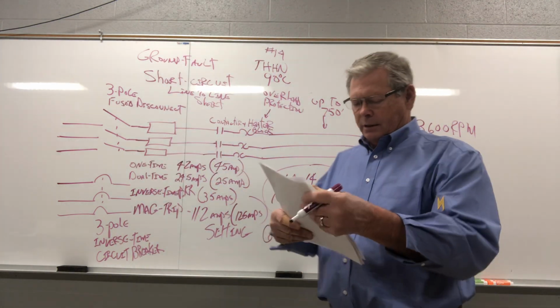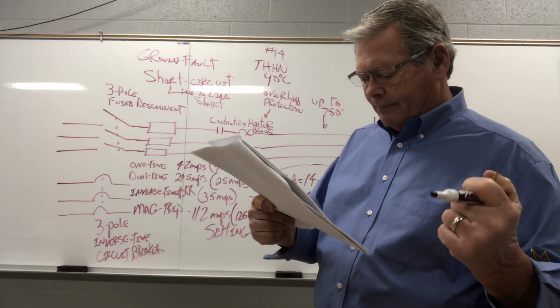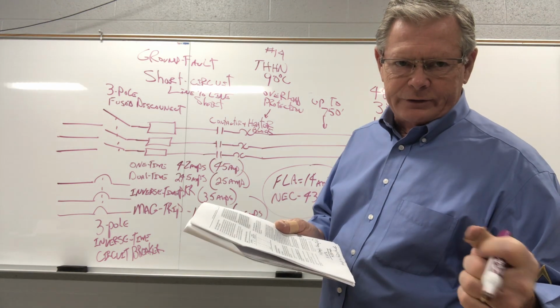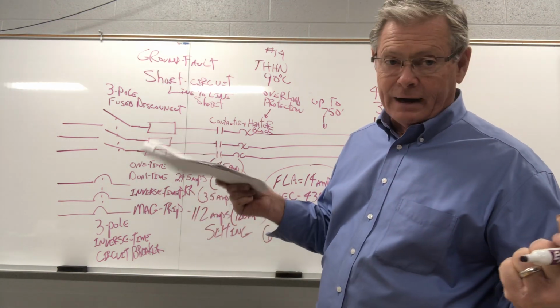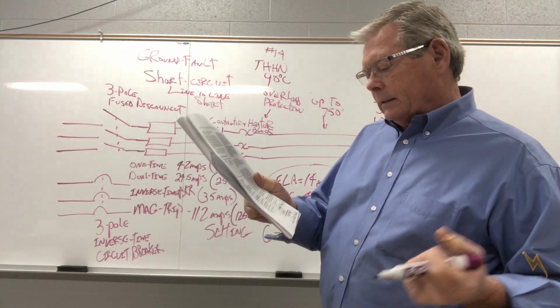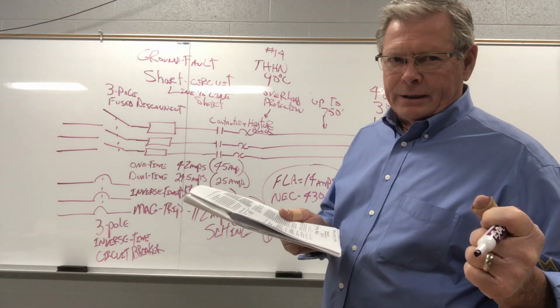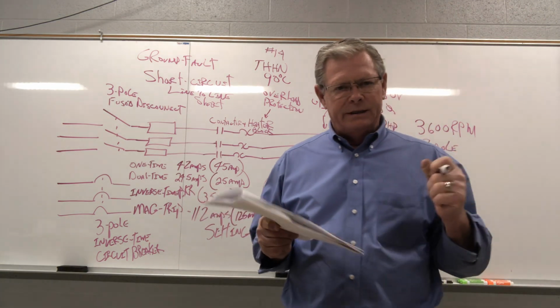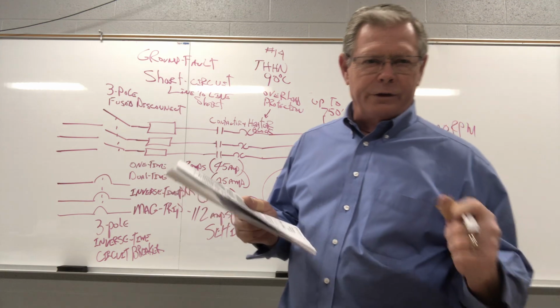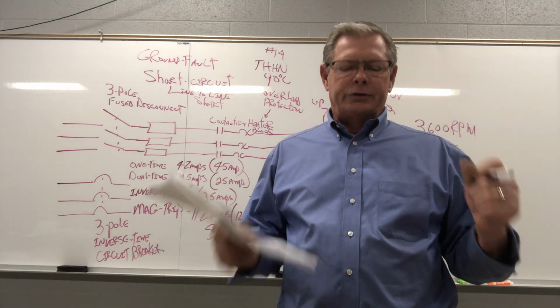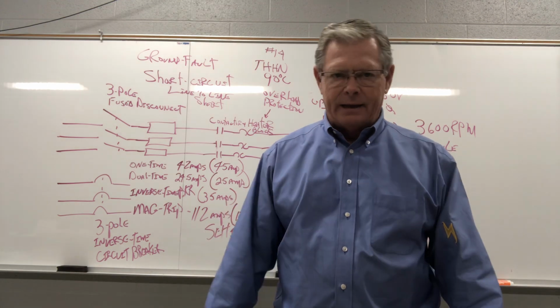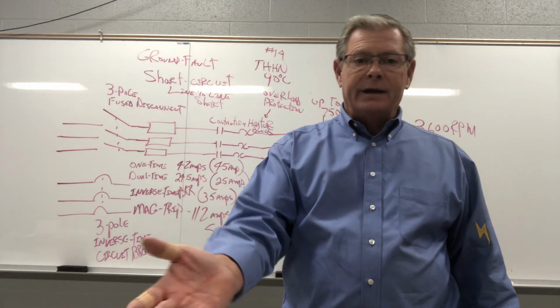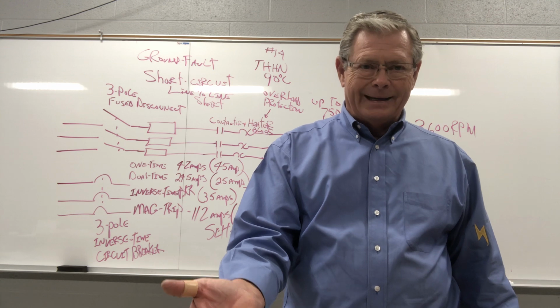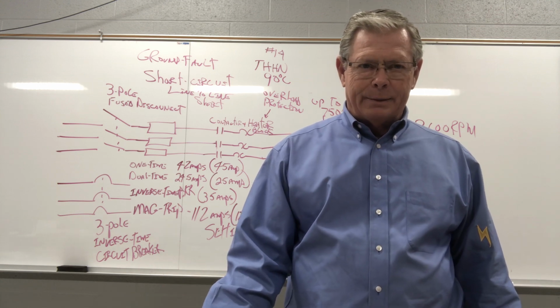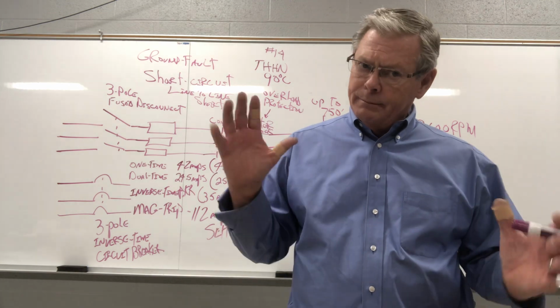Now, it's right here, it says separate overload device. What this says is, if you have motors that are marked with a 1.15 service factor or greater, most motors are a 1.15 or 1.2 or 1.35, or 40 degrees C rise over ambient or less. Now what that means is the 40 degrees C, that's how hot that motor runs when you're developing horsepower. So sometimes they'll call you and say, hey, this motor's so hot you can fry an egg on it. Well, if it is 100 degrees on a summer day and that motor is 40 degrees C over ambient, yeah, you can fry an egg on it, but the motor's built for that.